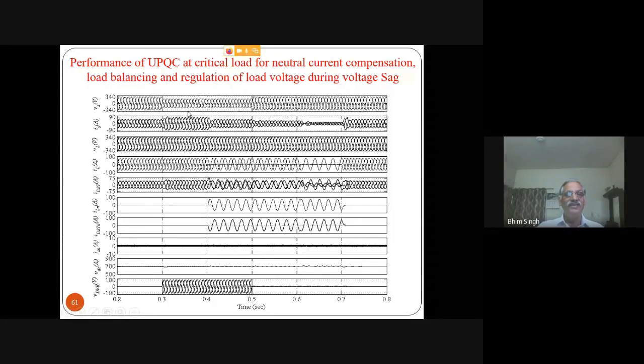You will find it very interesting, and of course, this is the injected voltage. Then you have a sag here also. And typically, you can think of it as a 3-phase 4-wire system, so you will have a neutral current. Typically the load neutral current appears, and the D-STATCOM forces a current exactly opposite to that, so that the neutral current in the supply is zero. So it takes care of that also.